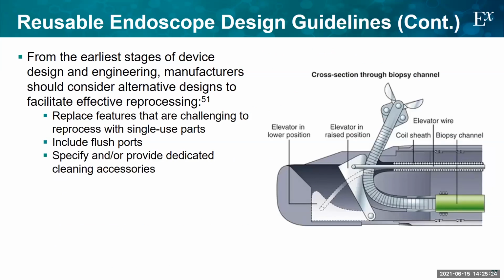And, from the earliest stages, the manufacturer should consider how they can replace these features that are challenging to reprocess with something that's single use, and putting in flush ports and just providing accessories that help to clean the devices. Here on the right is probably the biggest problem with a reusable endoscope, and this is what's called the elevator channel. So at some point you have to get this device, which is along the axis of the instrument, to go more or less perpendicular to it, to dive into that biliary duct.